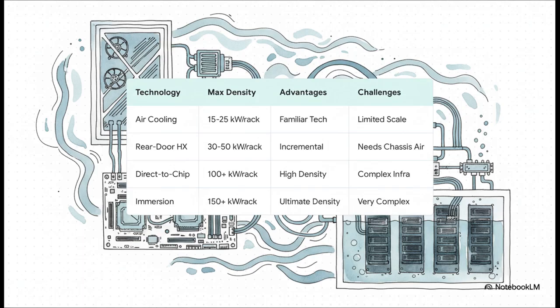Then there are rear-door heat exchangers. Think of them as radiators you bolt onto the back of your server rack. They're a great middle step, getting you up towards 50 kilowatts. Then you have our high-performance champion, direct-to-chip, for the densest AI workloads, but it requires more complex plumbing. And finally, you've got the ultimate solution, immersion cooling, where you literally dunk your servers in a special fluid. It gives you the absolute highest density, but it's also the most complex and specialized.